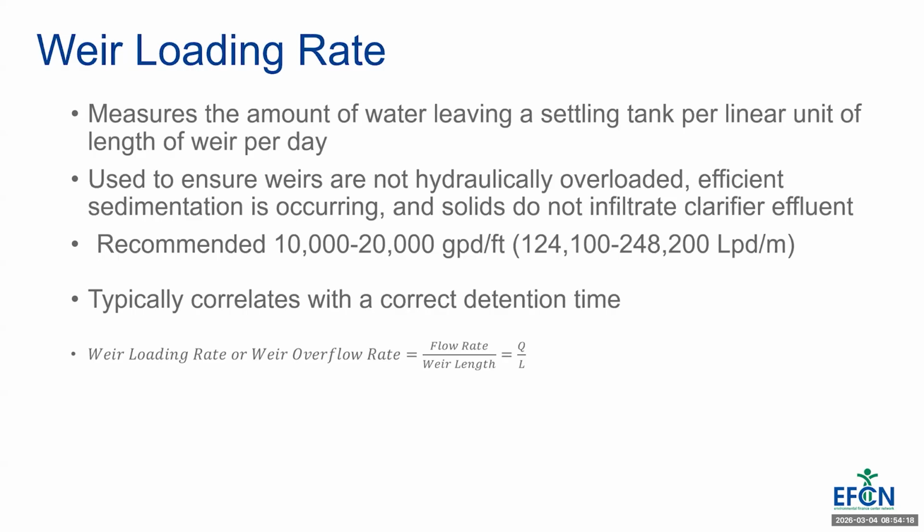And this typically correlates with your correct detention time. So what we were just talking about with detention time, if your detention time is not long enough, your weir loading rate's probably not going to be right. You're probably going to see issues with solids coming over the weir, solids not settling, things like that. So weir loading rate, or the weir overflow rate, depending on how it's worded, is your flow rate over your weir length.